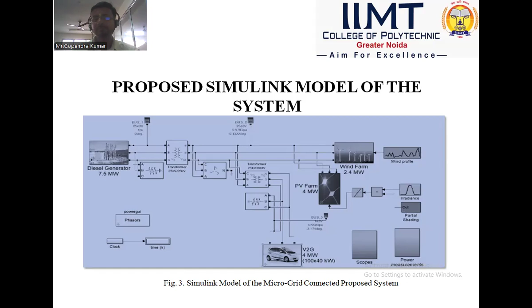The various parameters of the connected blocks are listed here: diesel generator of 7.5 megawatts; transformer 1 at 25 upon 25 kilovolt; transformer 2 at 25 kV upon 600 volt; bus bar 1; bus bar 2; PV farm of 4 megawatts; wind farm of 2.4 megawatts; EV load of 4 megawatts; frequency of 60 hertz; and grid supply of 320 AC.